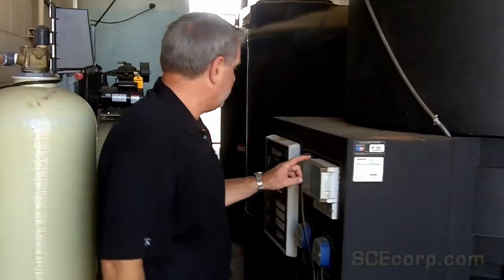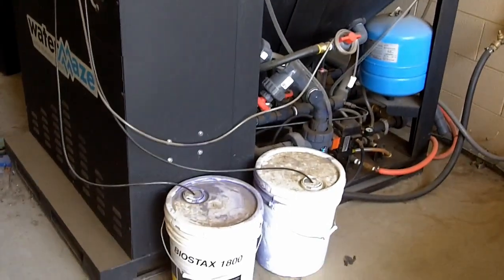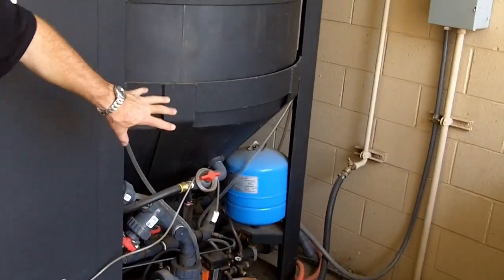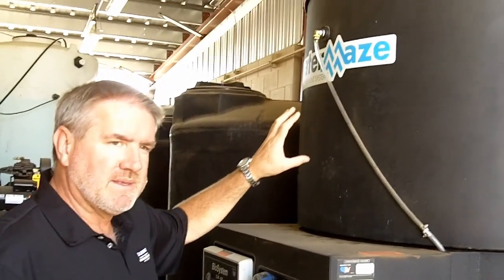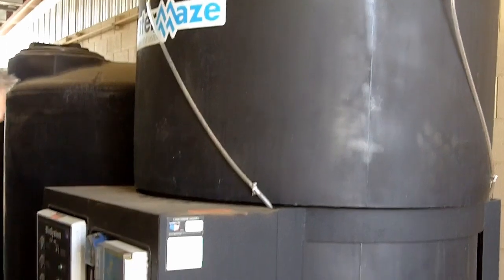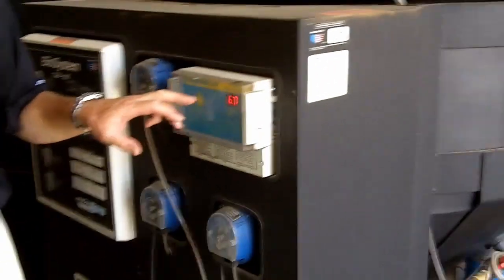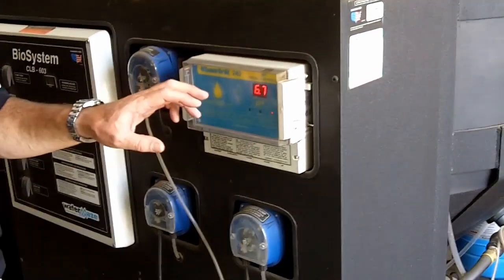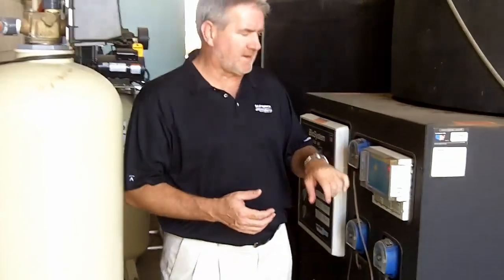Then from here we go into the CLB-603 system. This is a bio system — a full recycle module with all the pumps, transfer pumps, and air valves. We inject microbes into the system nightly. What that does is aerate the system — those microbes are digesting oils and hydrocarbons 24/7 while this is running. We've got a pH controller set at 6.7, which is really important to keep at neutral, because when you have a neutral pH, oils float and solids drop, and you get cleaner water.